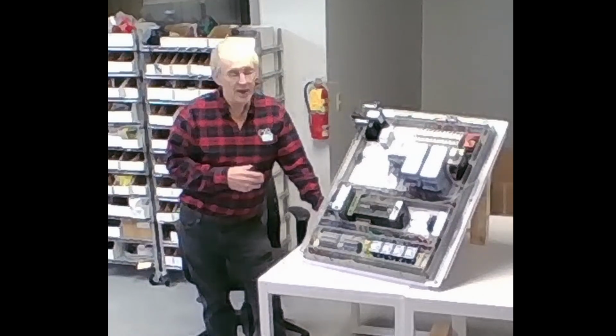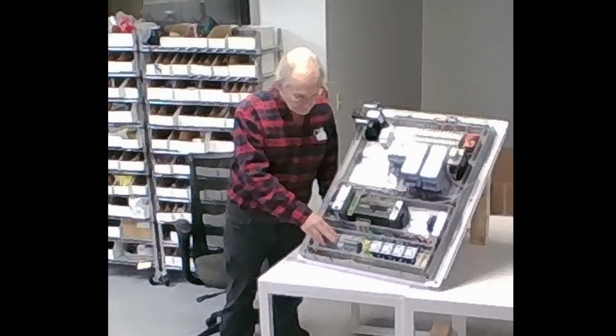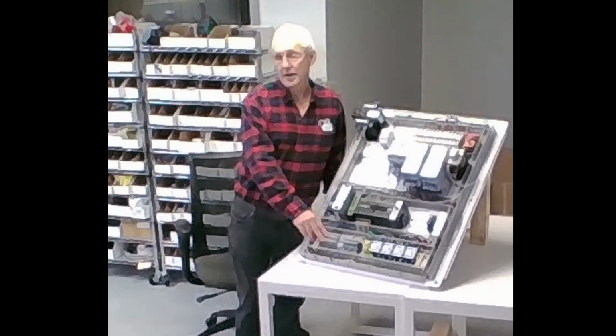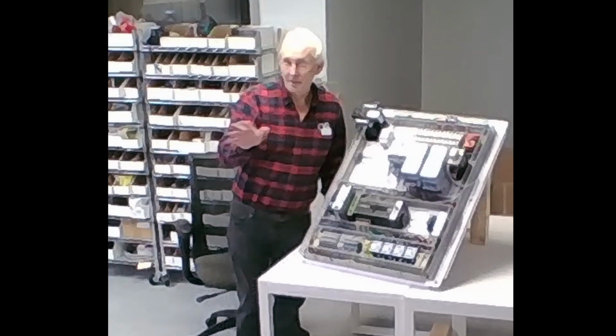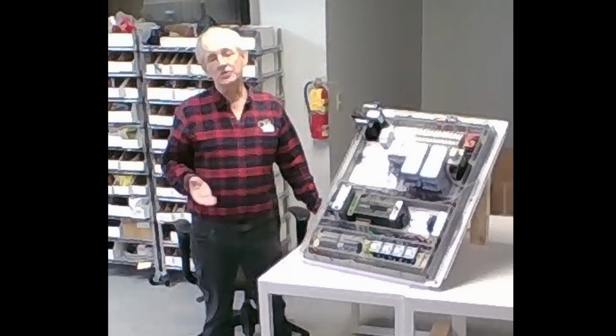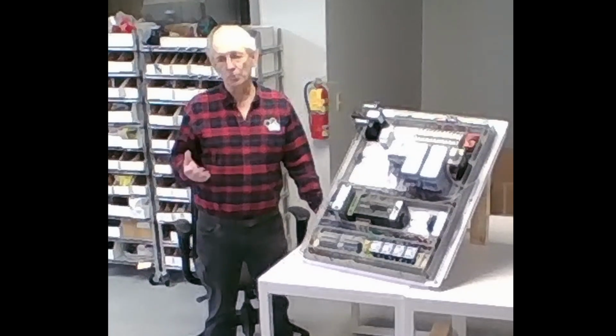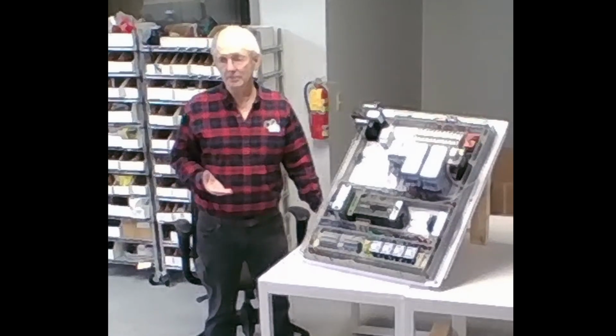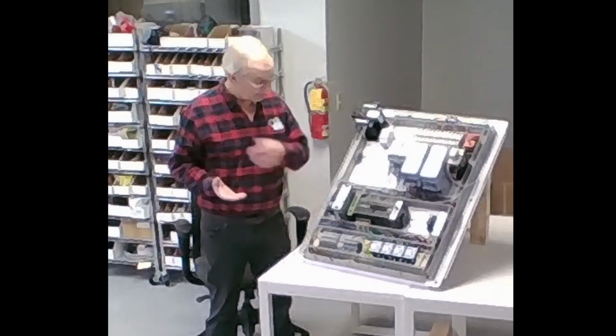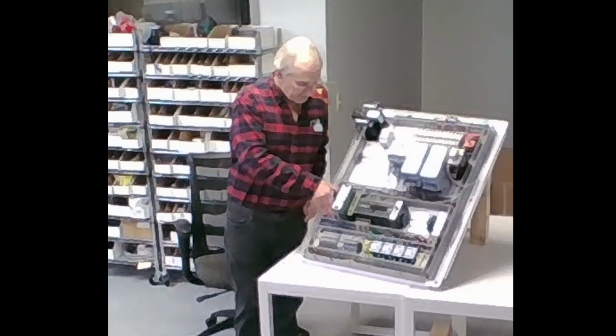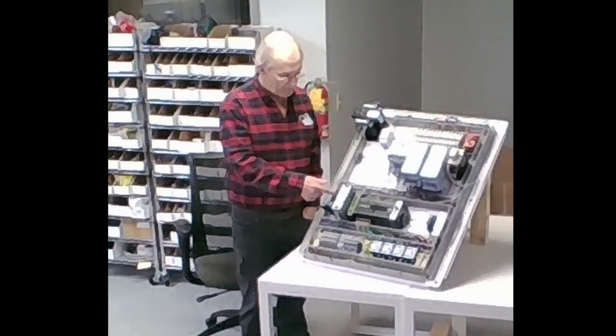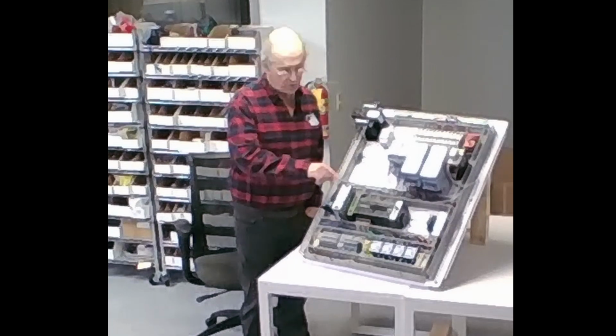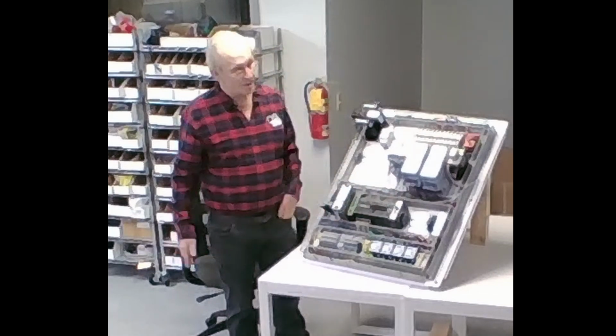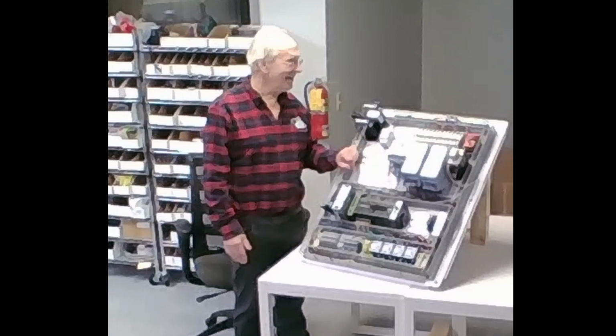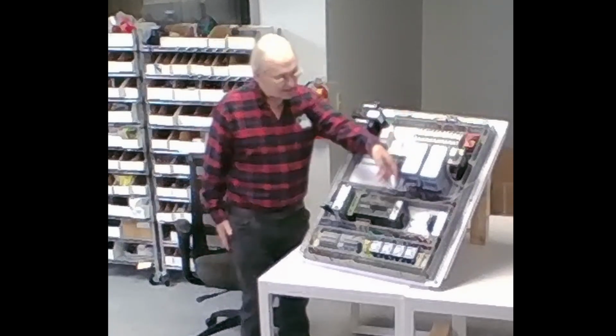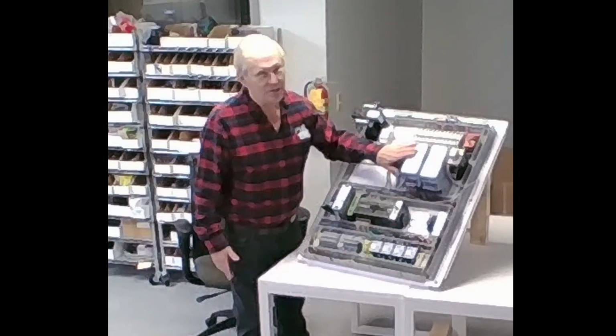In our case, all of our fuses are on the plus side. Whether the device is NPN or PNP, all the fusing is done on the plus side. That's just by convention. It's not an absolute rule, but typically the plus is always the fuse side. Another simple thing: the fuse holders we're using pull out like this, so the top is always the line side. In other words, power comes to the fuse at the top of all the devices here, except when they went to VFDs. These two VFDs have it on the top to the bottom, and contactors are always on top to the bottom. But then they went to bigger VFDs and put everything on the bottom.